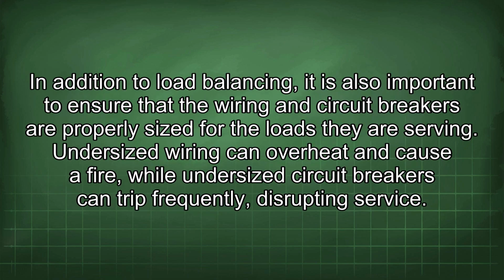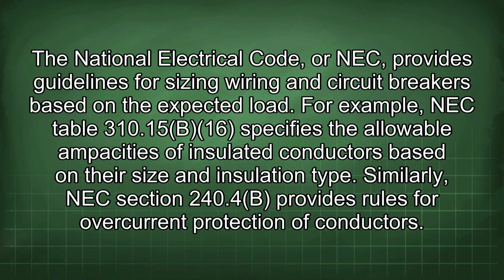In addition to load balancing, it is also important to ensure that the wiring and circuit breakers are properly sized for the loads they are serving. Undersized wiring can overheat and cause a fire, while undersized circuit breakers can trip frequently, disrupting service. The National Electrical Code, or NEC, provides guidelines for sizing wiring and circuit breakers based on the expected load. For example, NEC Table 310.15(B)(16) specifies the allowable ampacities of insulated conductors based on their size and insulation type. Similarly, NEC Section 240.4(B) provides rules for overcurrent protection of conductors.